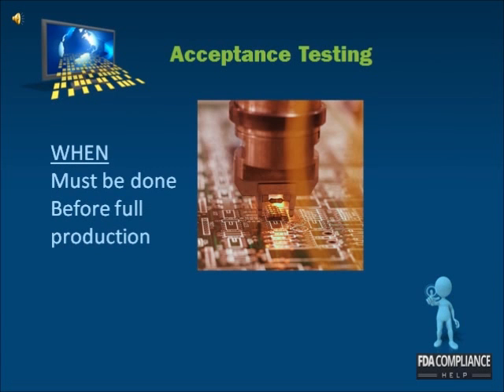Before the device is ready for full-scale production, the test and inspection decisions shall be completed and documented as test and inspection instructions or acceptance procedures, and approved for use. It is a violation of the United States Food, Drug, and Cosmetic Act to place inadequately evaluated devices into commercial distribution. It is also a violation of the Quality System Regulation to allow test and inspection procedures to evolve during ongoing production.